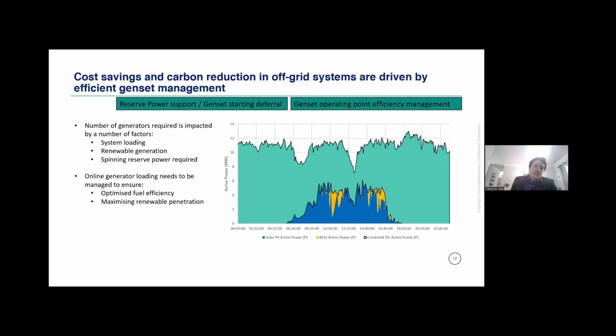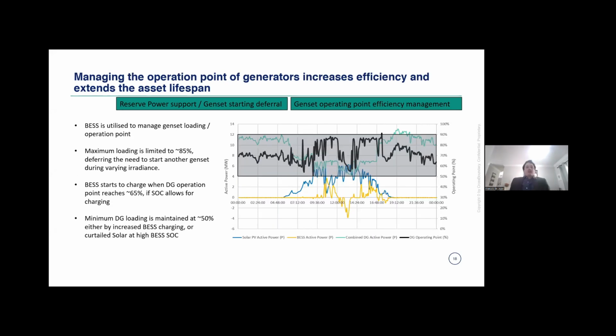So the online generator loading needs to be managed so that we can ensure an optimized fuel efficiency and not run an additional generator just for the sake of reserve, and also to maximize renewable penetration. Because if we have too many generators online, obviously the amount of renewable generation we can inject into the system is also limited by the minimum loading of the gensets online. So managing the operation point of the generators increases the efficiency and also extends the asset lifespan.